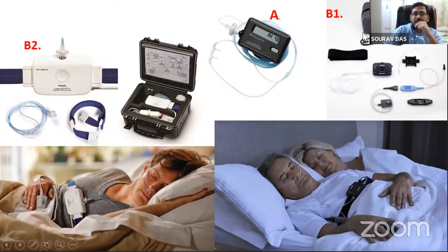Now, these B1 and B2 are level 3 devices of various companies. They measure, in addition to the airflow, the oximeter. We can see the oximeter is there, and here too. So these machines are capable of measuring the airflow, the oxygen desaturation, along with the pulse rate, and we can see there is a chest or abdominal belt which has been put. It also measures the respiratory effort. Now, the newer models can also have a position sensor, which will say whether the person is sleeping on their right, in a supine position, or on their left. This data can be obtained using the latest models.